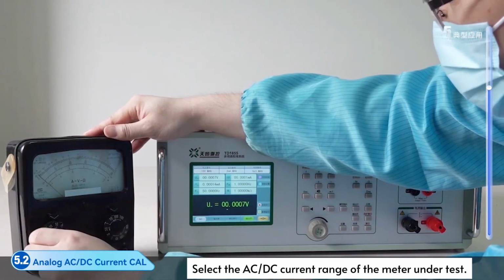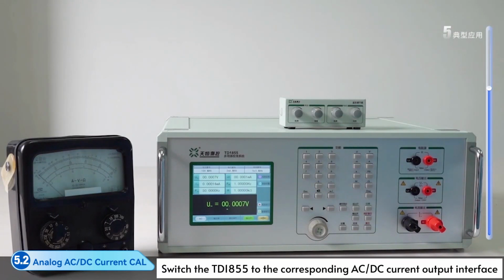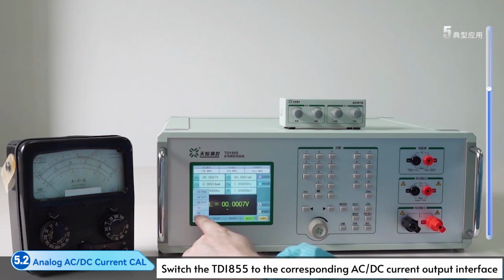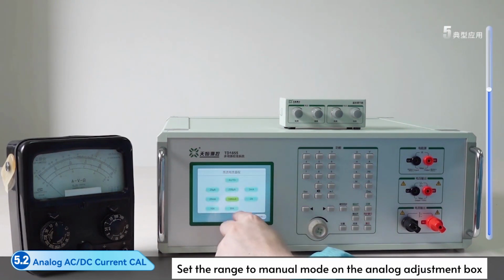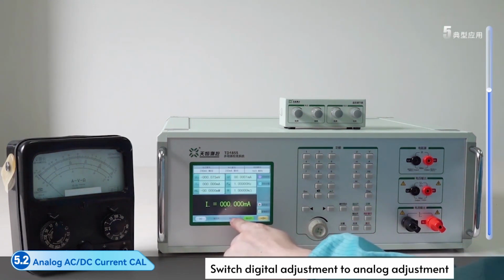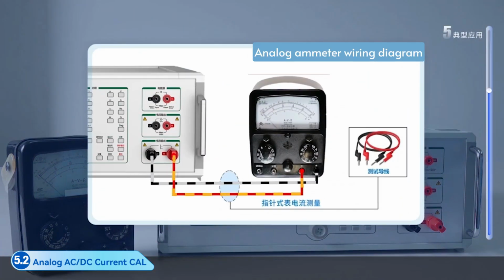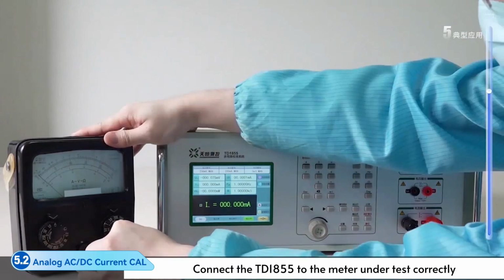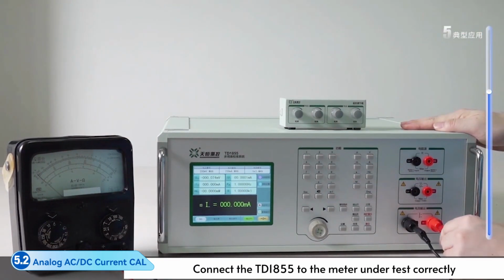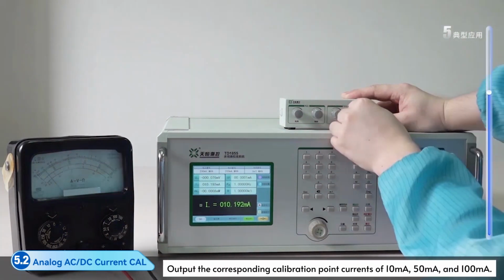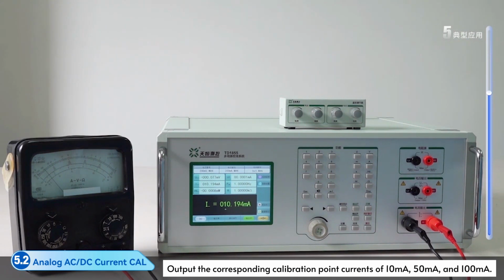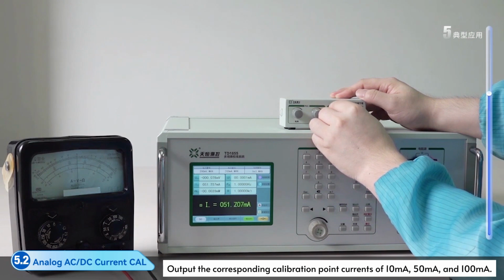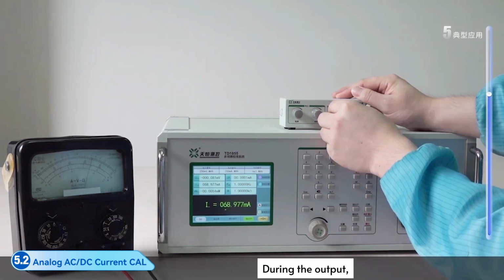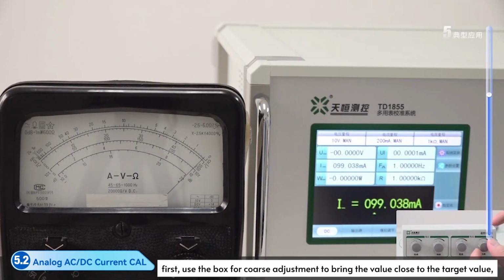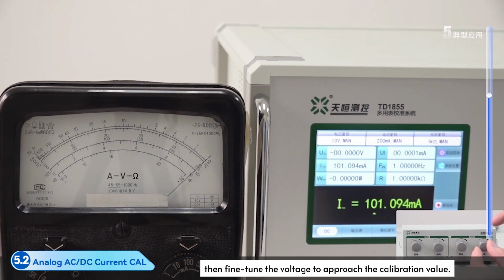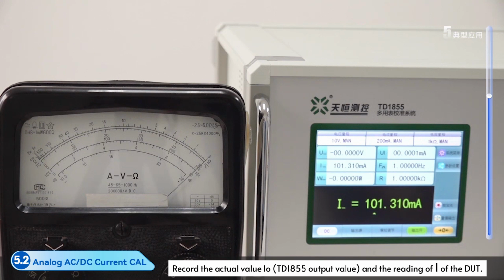Select the AC/DC current range of the meter under test. Switch the TD1855 to the corresponding AC/DC current output interface. Set the range to manual mode. Switch digital adjustment to analog adjustment. Connect the TD1855 to the analog meter correctly. Output the corresponding calibration point currents of 10 mA, 50 mA, and 100 mA. During the output, first use the box for coarse adjustment, then fine-tune to approach the calibration value. Record the actual value and the reading of the DUT.